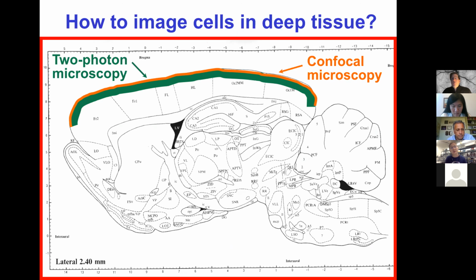So there's improvement to be made. People are exploring 3-photon imaging in the field, and there are different wavelength requirements for 3-photon imaging, as well as the fact that it's typically good to have amplification of the laser pulses. But for conventional imaging, typical parameters might be an 80 megahertz repetition rate and 800 to 850 nanometers wavelength of excitation.